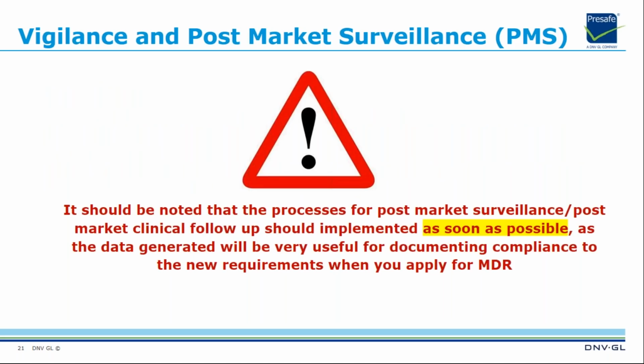It should be noted that the processes for post-marketing surveillance and post-market clinical follow-up should be implemented as soon as possible, as the data generated will be very useful for documenting compliance to the new requirements when you apply for MDR. Manufacturers need to review their procedures for PMS and ensure that the responsibility for the provision of this additional data and associated support is clearly established. This is likely to require additional resources in functions that support products on the market, such as regulatory and medical affairs.